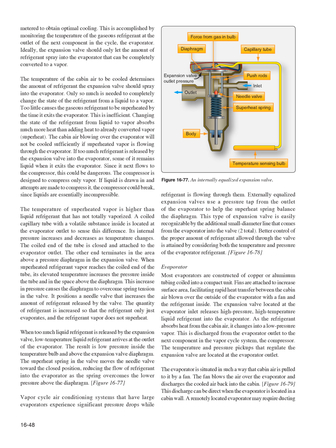A coiled capillary tube with a volatile substance inside is located at the evaporator outlet to sense this difference. Its internal pressure increases and decreases as temperature changes. The coiled end of the tube is closed and attached to the evaporator outlet. The other end terminates in the area above a pressure diaphragm in the expansion valve. When superheated refrigerant vapor reaches the coiled end of the tube, its elevated temperature increases the pressure inside the tube and in the space above the diaphragm.